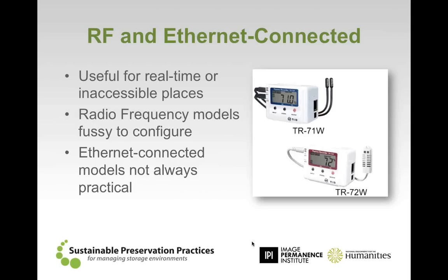We have run into one instance that I know of where somebody was using an Ethernet logger within their space, and they wanted to move the logger deeper into the space, so they had the wire going across the floor. And whether it was for cleaning or moving, somebody had unplugged the logger for the evening. Generally, if these loggers get unplugged from their source, they have a 3 to 4 hour backup. But after they were done, the person never plugged it in, so they wound up 2 or 3 days later realizing they had lost some of that information. So it's one thing to keep in mind.